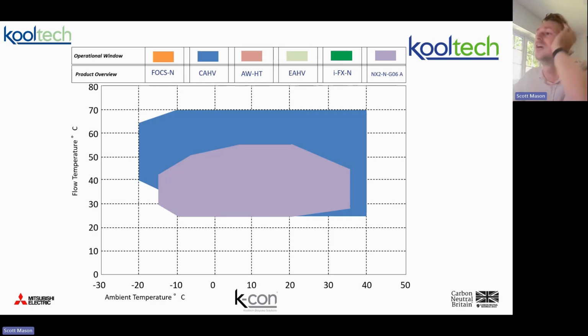It's just that little bit too low. But this unit, if it's on a heating circuit, is better suited than the CAHV generally, because I can build my circulating pump in, I can flow at 50 degrees all the time anyway, so actually it'll do heating. My performance curve probably is going to be weather compensated and looks a little bit like this. So the CAHV will do it, but it's at the lower end of the operating window. The NXN will definitely do it, and it's banging its operating window.